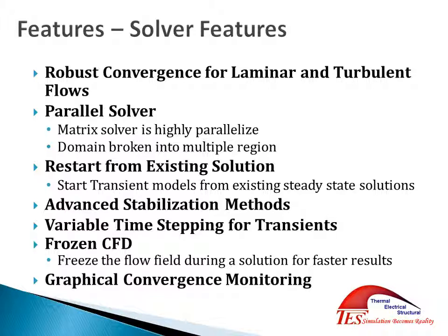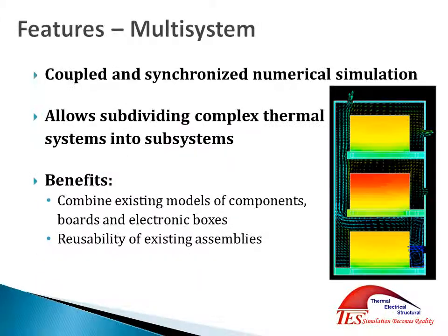Frozen CFD means that you can actually, at any point during your analysis, stop your flow calculations and just maintain that velocity. So if you think that the temperature is already fairly stabilized, we're not going to have much change in our natural convection. Or if it's a forced convection, you can stop those at any point and then continue to update for temperature, both for your solid and your fluid. So your fluid temperatures will still update. It's just the momentum portion of the fluid will not be updated.